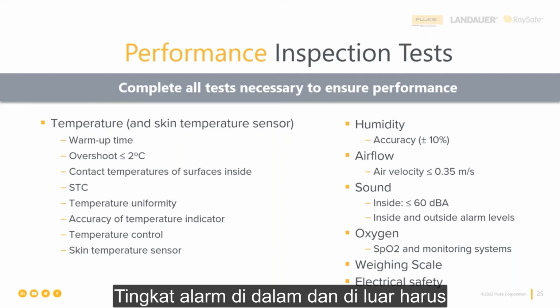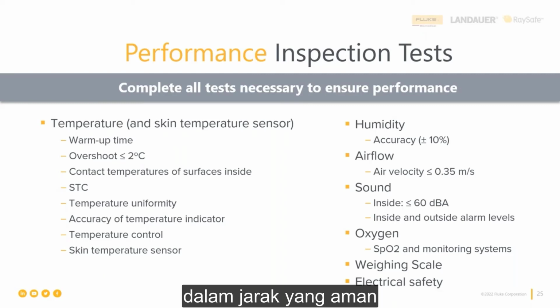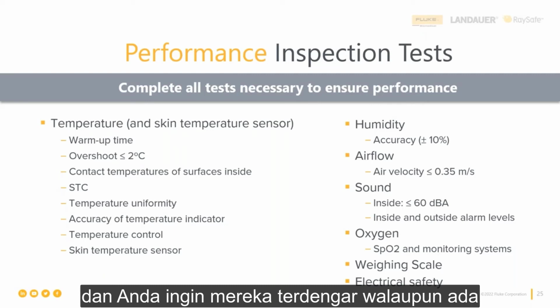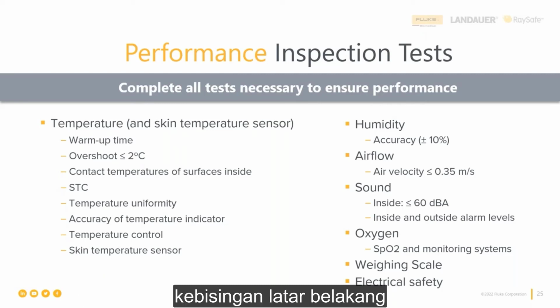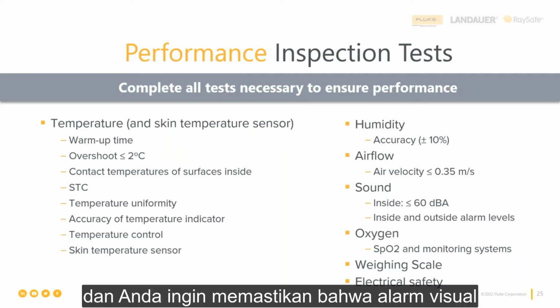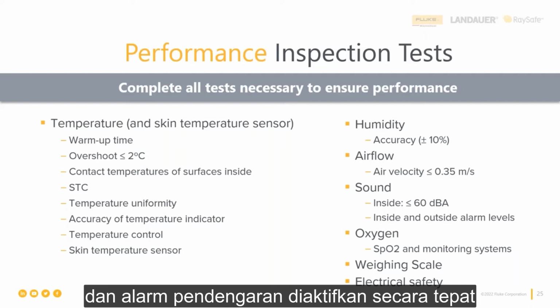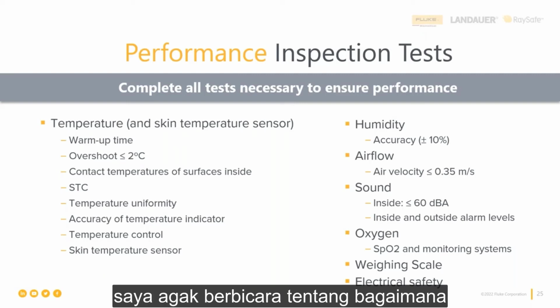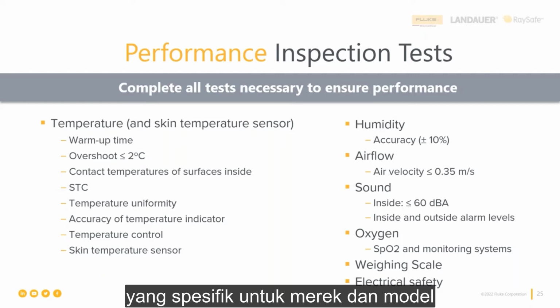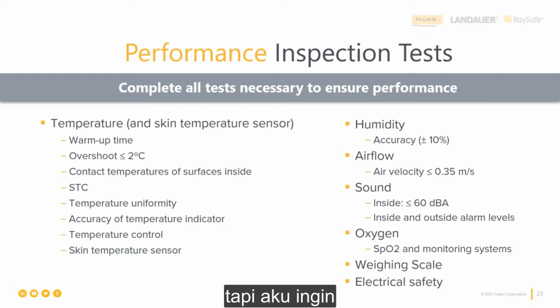Inside and outside alarm levels should also be measured to ensure that they are within a safe range. And you want them to be audible over any background noise, since it's oftentimes not only the incubator that's in this room. In terms of oxygen, again, you want to check oxygen concentration to validate that it is within the acceptable range. And you want to ensure that the visual and auditory alarms are appropriately activated. I kind of talked about how those are specific to brands and models, but I did want to note that here as well.